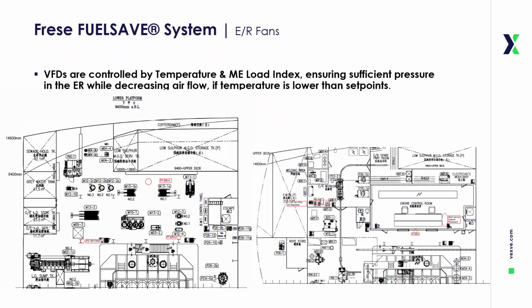Within the Frese FuelSave system, the engine room ventilation fans are integrated into the same advanced control logic as the pumps and valves. Each fan is equipped with a variable frequency drive, which allows the system to continuously adjust fan speed according to real-time operational data. Fans may also be operated in a cascade mode.